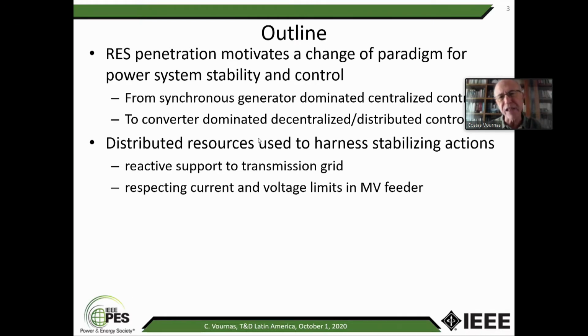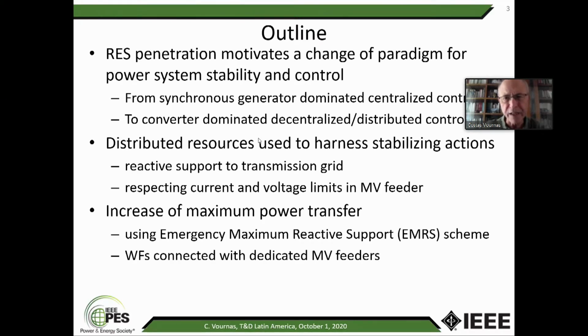So it is, as in the case of synchronous generators, we have to respect synchronous generator operation to give ancillary services to the network. The same is true in case that we give these services through the reactive support of wind farms. So in particular, I will explain in a minute that the goal is to use an emergency maximum reactive support scheme. So in case the voltage in the transmission system is dropping, we can have an increase in the maximum power transfer, and this increase in the maximum power transfer will be done through the wind farms that are connected with dedicated medium voltage feeders.